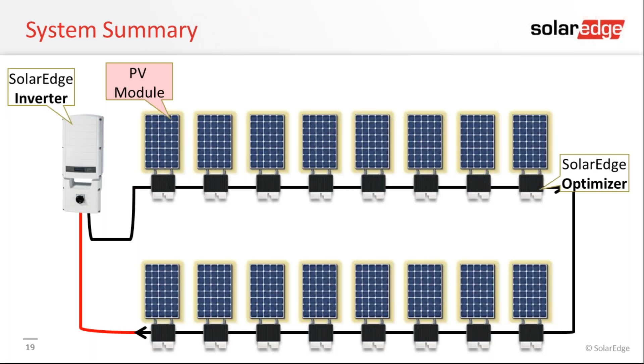So under normal operation, our SolarEdge inverter is working, our PV module is working, and our SolarEdge optimizer is working. If the system is on, the optimizers send a fixed voltage to the inverter. That DC voltage for commercial products is 850 volts.